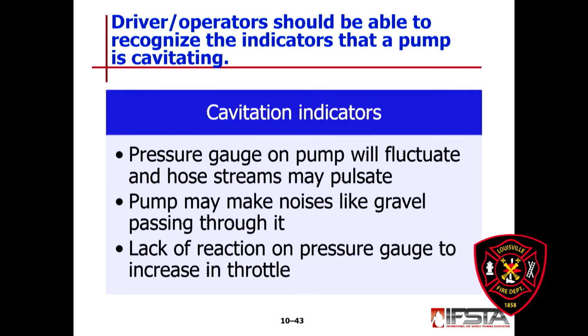You should be able to realize when your pump is beginning to cavitate, and some things are going to start happening. Your pressure gauge on your pump will start to fluctuate. Maybe air or hose streams start to pulsate or jump around as you move air pockets through the hose lines. The pump may sound like there's gravel passing through it. What's happening there is air bubbles are getting into the pump, and once they are put under pressure in the pump, they collapse, which makes it sound like gravel passing through your pump. You also try to increase your throttle and you're not getting any more pressure, so now you're overwhelming your supply. These are all indicators of cavitation.